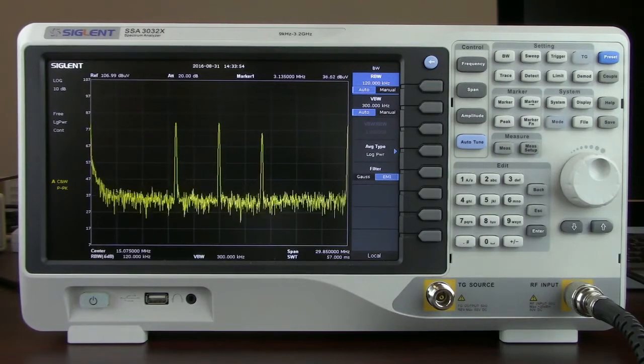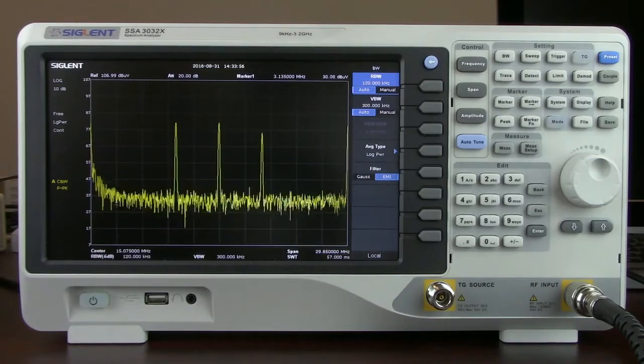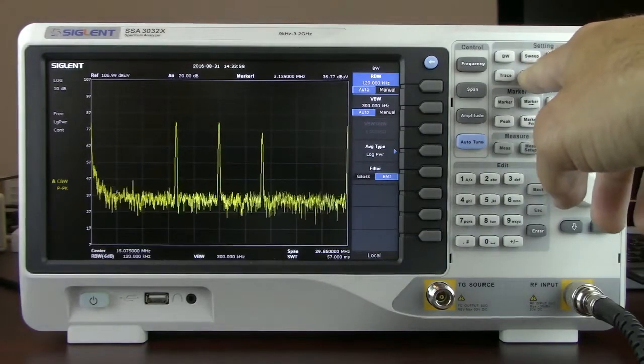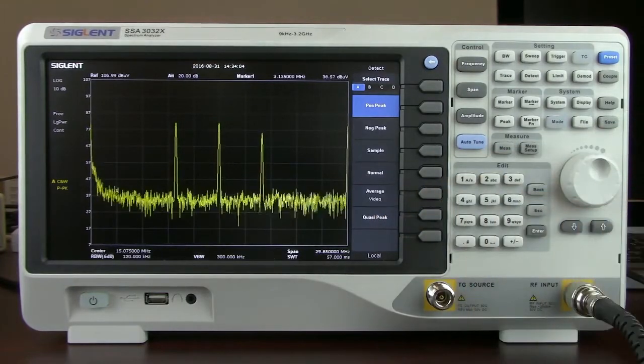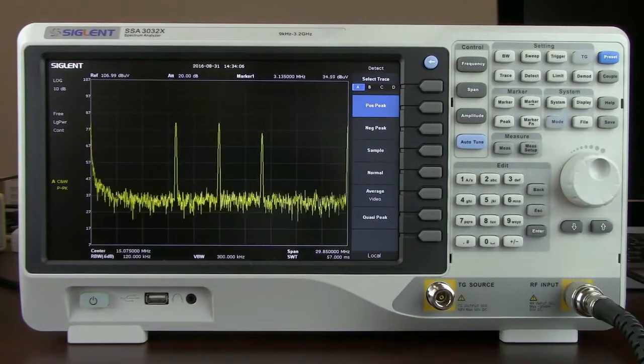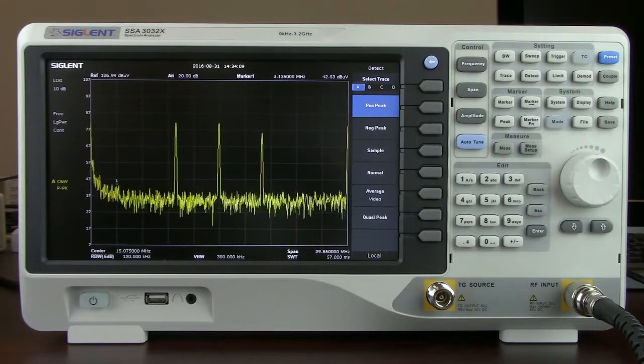Those are defined bandwidths for the FCC as well as CISPR measurement standards for compliance. And then we're also going to be able to activate the quasi-peak detector. So we can press detect and now you'll see that the quasi-peak detector is available and we can select that.